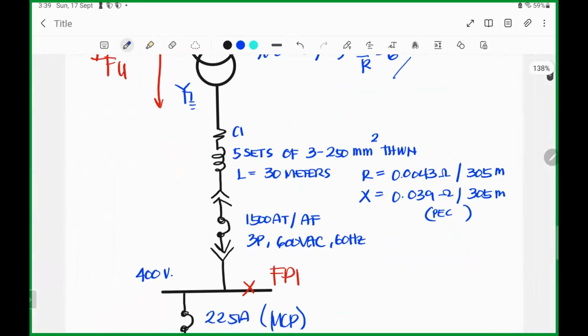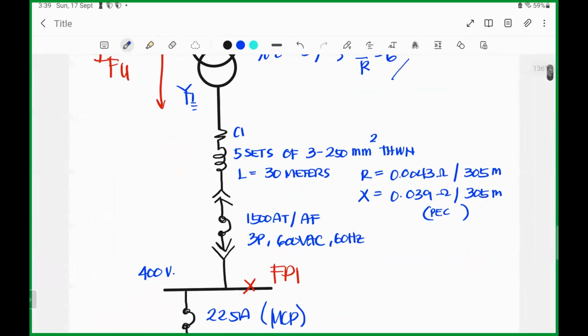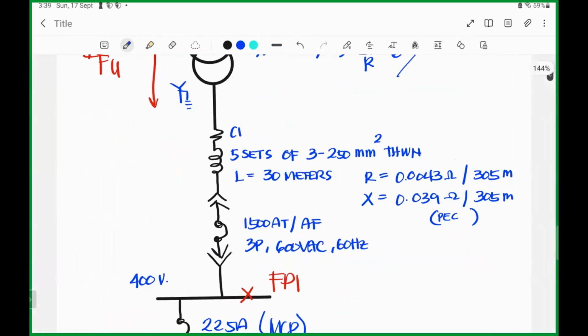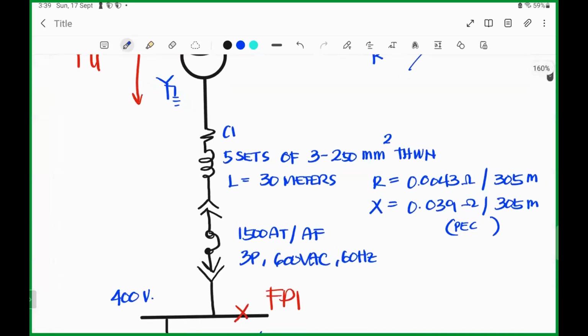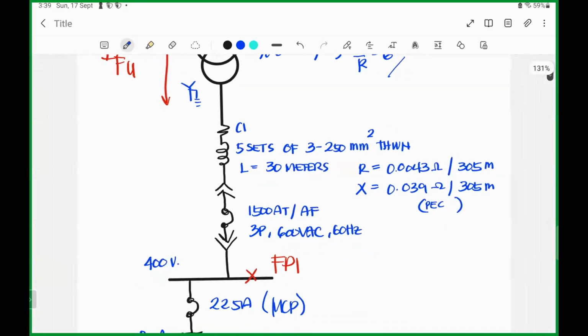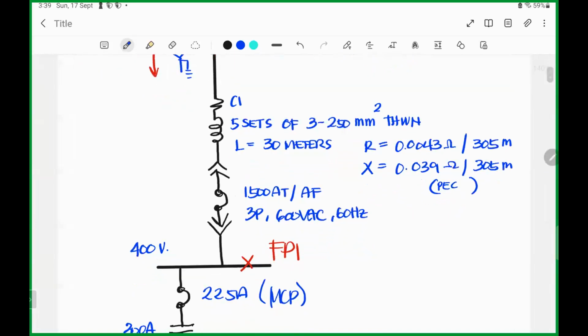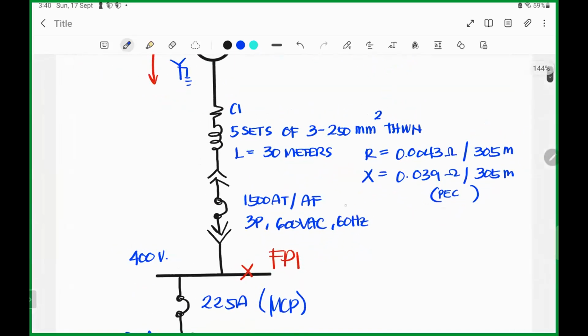So assume lang din naman to, for discussion purposes only. So my cable 1 is 5 sets of 250 mm square THWN. The length is 30 meters. So I use the R and X values for the cable in PEC. Makikita to sa PEC natin. Resistance of 250 mm is 0.0043 ohms per 305 meters, and the reactance is 0.039 ohms per 305 meters. So I assume that is a 1,500 ampere trip. Plot din natin mamaya ito in a manual way.